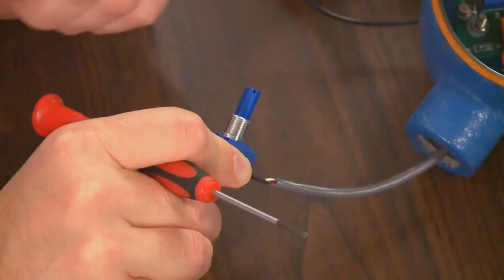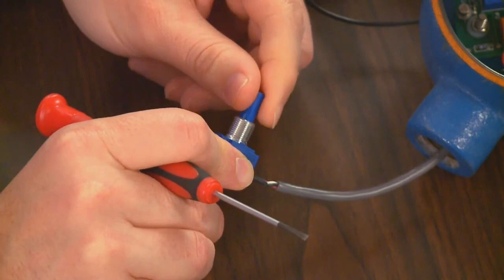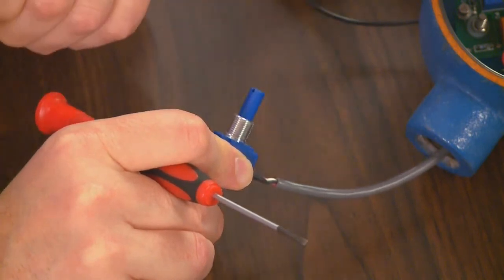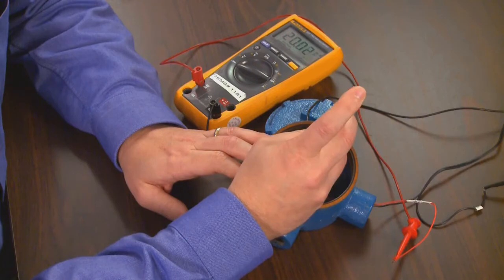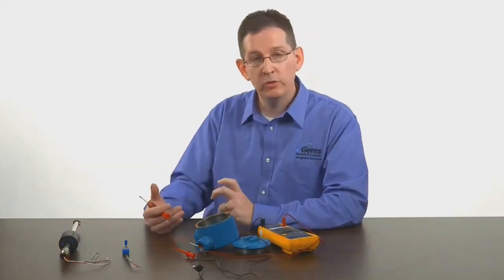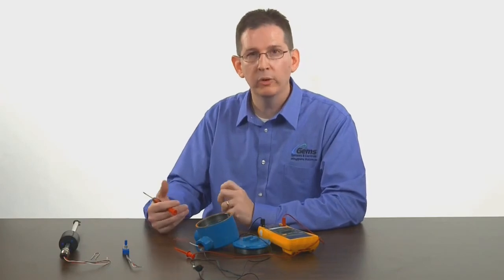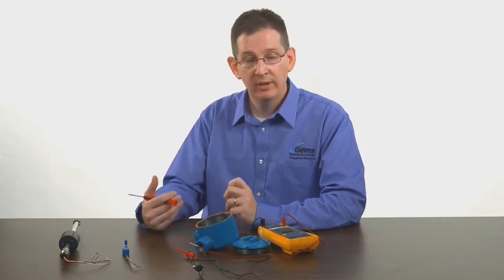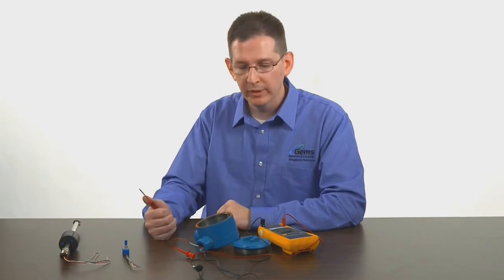If we bring the potentiometer fully clockwise, you'll notice that the output has actually changed. And we tweak that back towards the 20 milliamp point. As I said, doing that two or three times will pull that into your 4 and 20 points. Once you're done, your unit is fully calibrated.